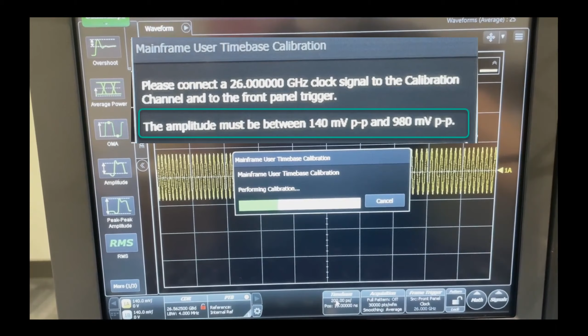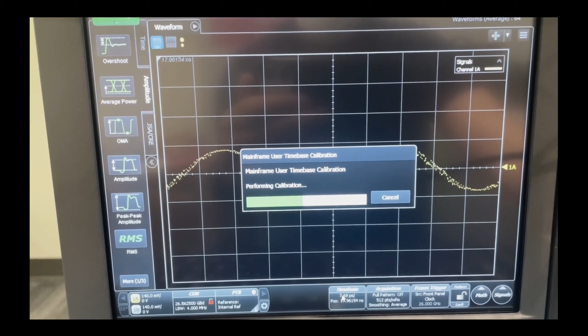If you try to do a mainframe user timebase calibration and the DCA has not been on long enough, you will get a warning and it'll give you a timeout. Now starting calibration. This doesn't take very long. It goes pretty quick. So it starts with the 26 gigahertz tone, which we've already set up. And again, they'll give you a guideline on the amplitude, and you want to make sure that your amplitude is in the ballpark of what it's saying here. It's pretty easy to do. So this is the process.